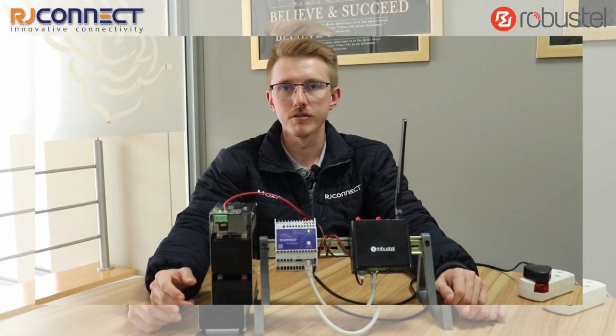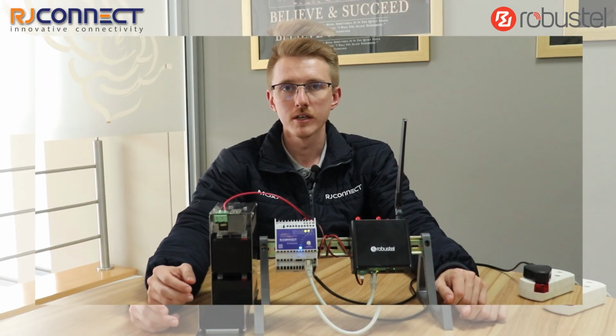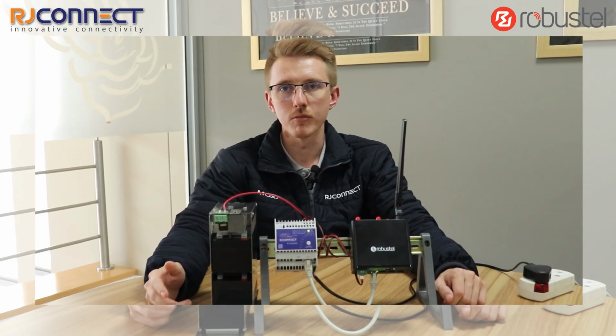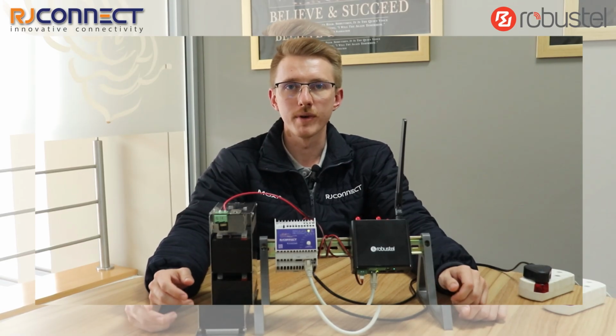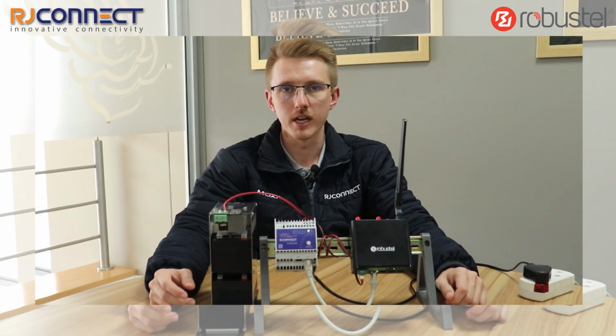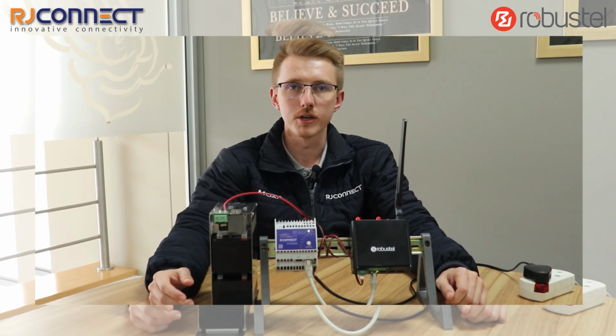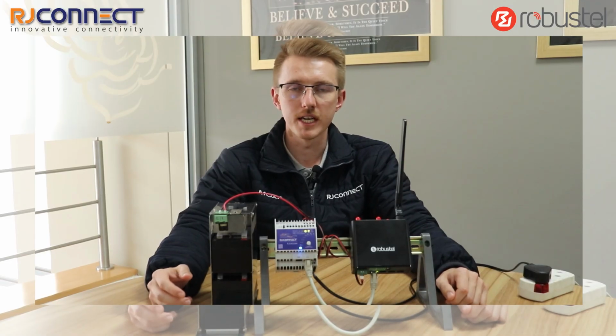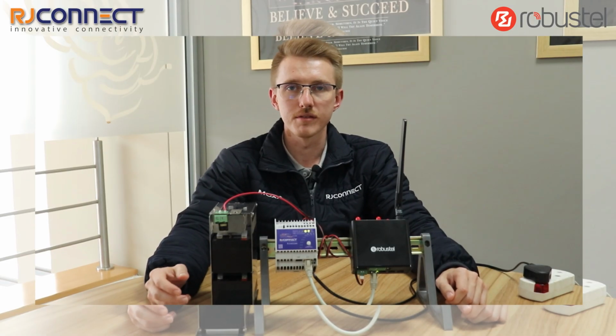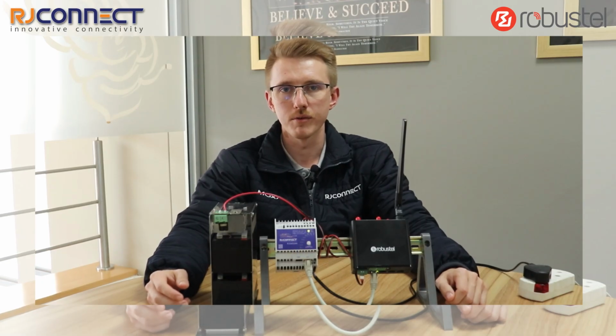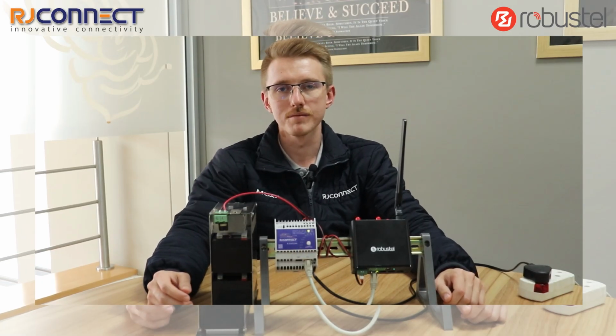This demonstration has shown the RJU6024A operating as an all-in-one 24-volt DC UPS, charger, and monitoring device. We confirm normal mains operation, local monitoring from a laptop through the web server, remote monitoring through the Robustel R1520 connection, battery backup during a simulated mains failure, diagnostics visibility, and automatic recovery when main power is restored.